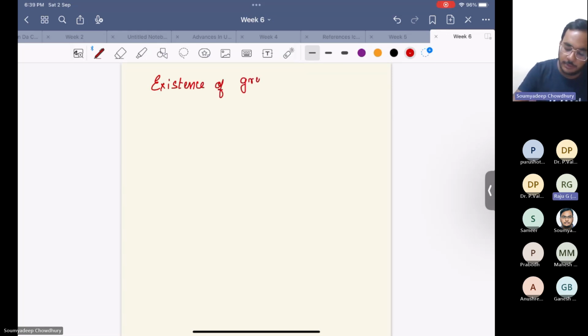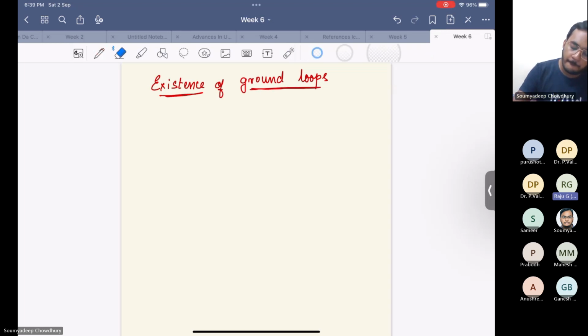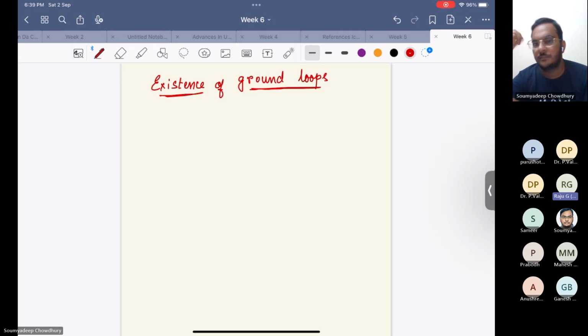I have some doubts. Yes, clear. Suppose the lightning comes on a building, and we have provided a lightning arrestor, and the lightning impulse comes to the ground, and because of the high frequency and the lambda condition, where we have multiple wavelengths repeated, multiple pulses will be there, and the ground potential will increase. And suppose a person walks around that particular place where it is grounded, the step voltage will be more, and a person will be electrocuted. Yes, there are chances, yes you're correct, there are chances of getting electrocuted. Therefore we may have to give a very low impedance so that the ground voltage is very low. Yes, correct, we have to provide a low impedance path for this lightning impulse wave. Thank you sir, thank you.